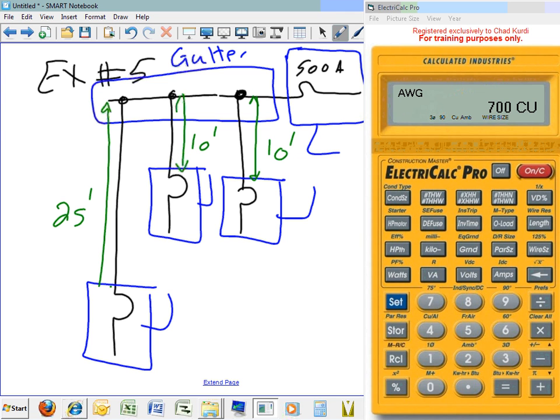Why would we tap? To save money. What does tap mean? Everybody knows what a tap means? A tap is when you take a number 16 conductor and tie it to a number 12. It's a tap with no overcurrent protection device. You take a 500 kcmil conductor and physically, mechanically tie it to a 2000 kcmil conductor. That's a tap. Every time you tie a conductor to another conductor of a different size, that's a tap. If you tie it through a circuit breaker, it's not a tap. If I have a 500 amp circuit breaker right here, tie it to 200 amp, and put a feeder after the circuit breaker right in here, that's not a tap.